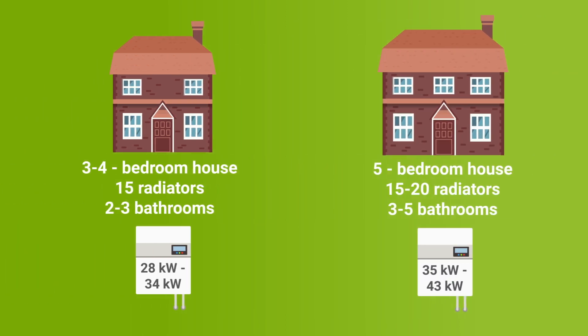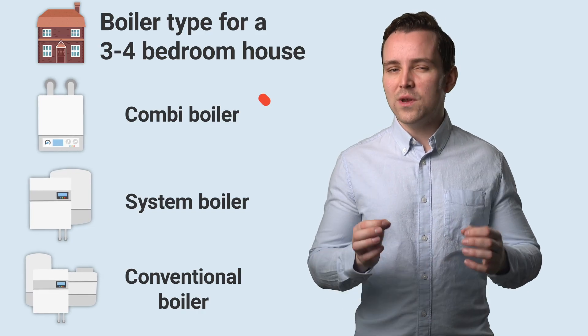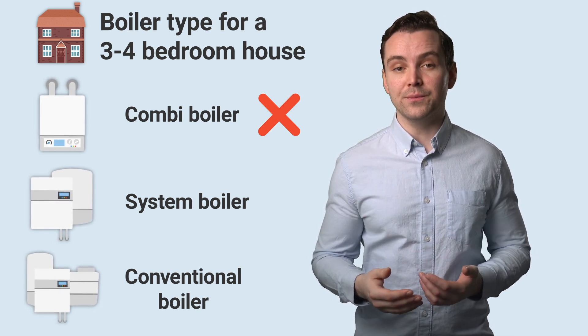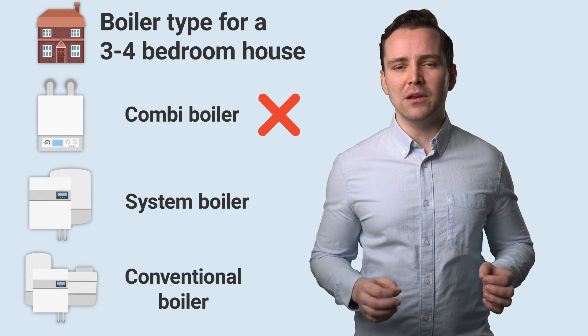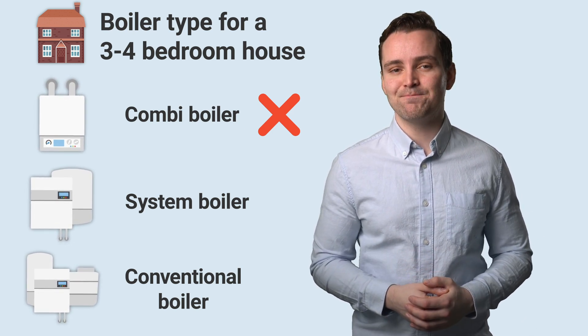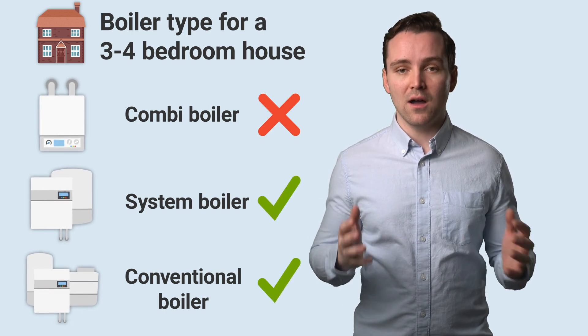While a large five-bedroom home with 15 to 20 radiators and three-to-five bathrooms will require a boiler with an output of between 35 and 43 kilowatts. It's worth noting that we don't recommend combi boilers for homes that have three-to-four bedrooms and multiple bathrooms, as they are usually not capable of meeting the high hot water demands a property of that size provides. In these cases, system and conventional boilers are recommended.